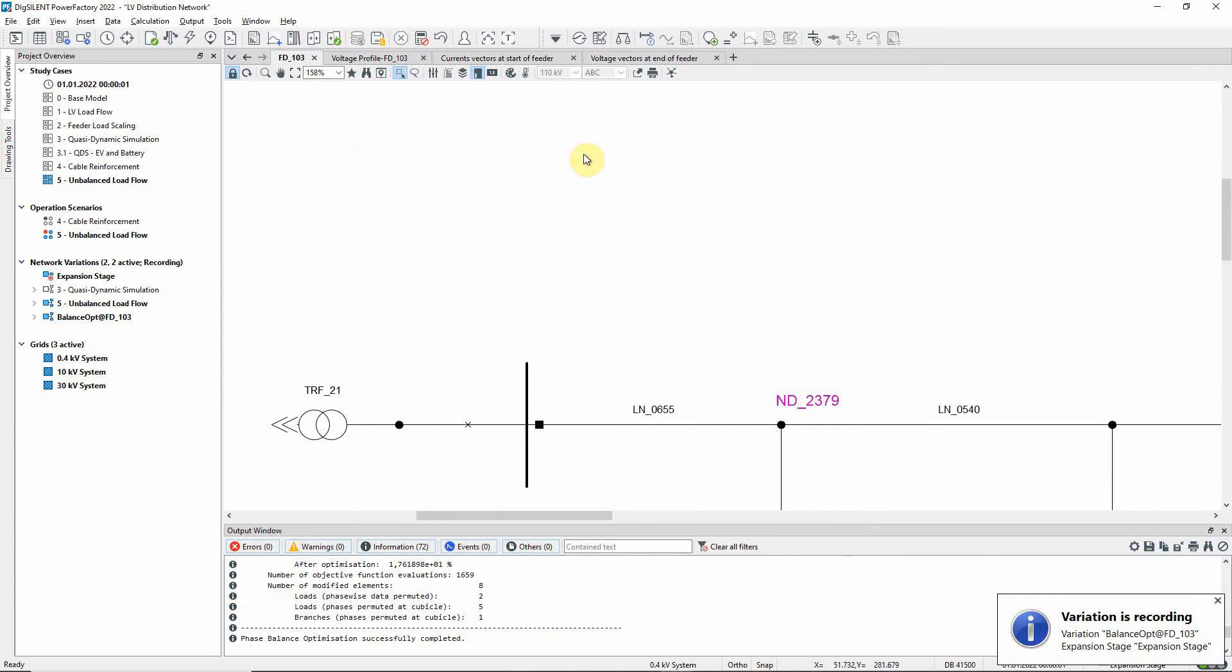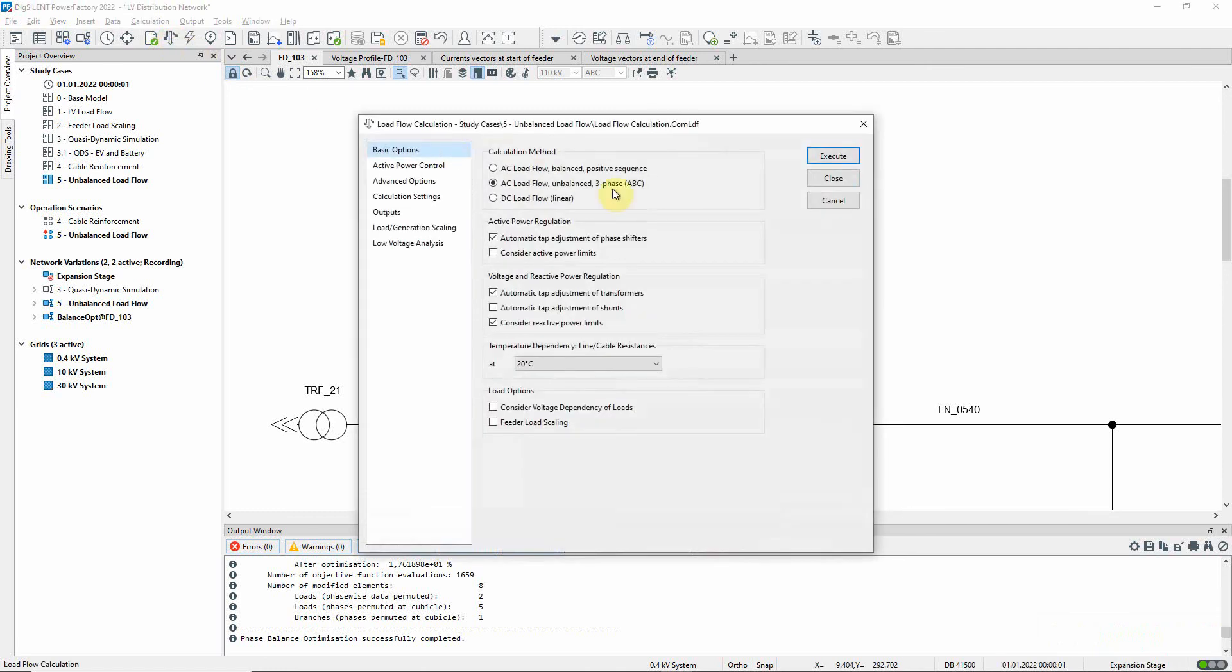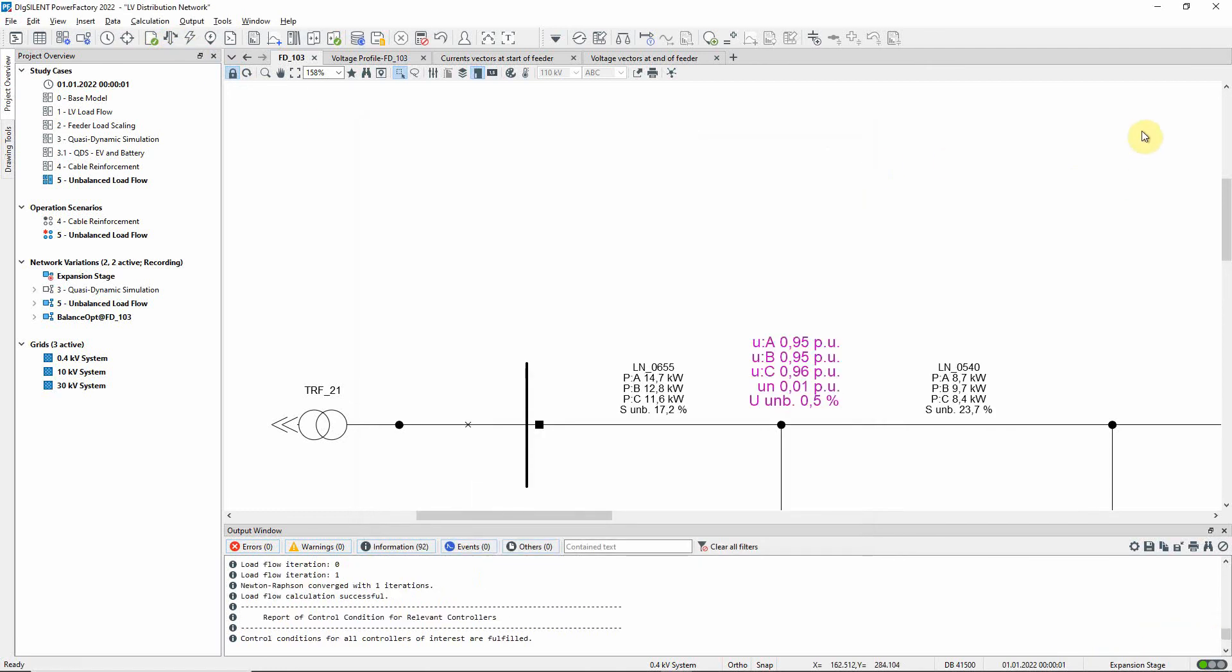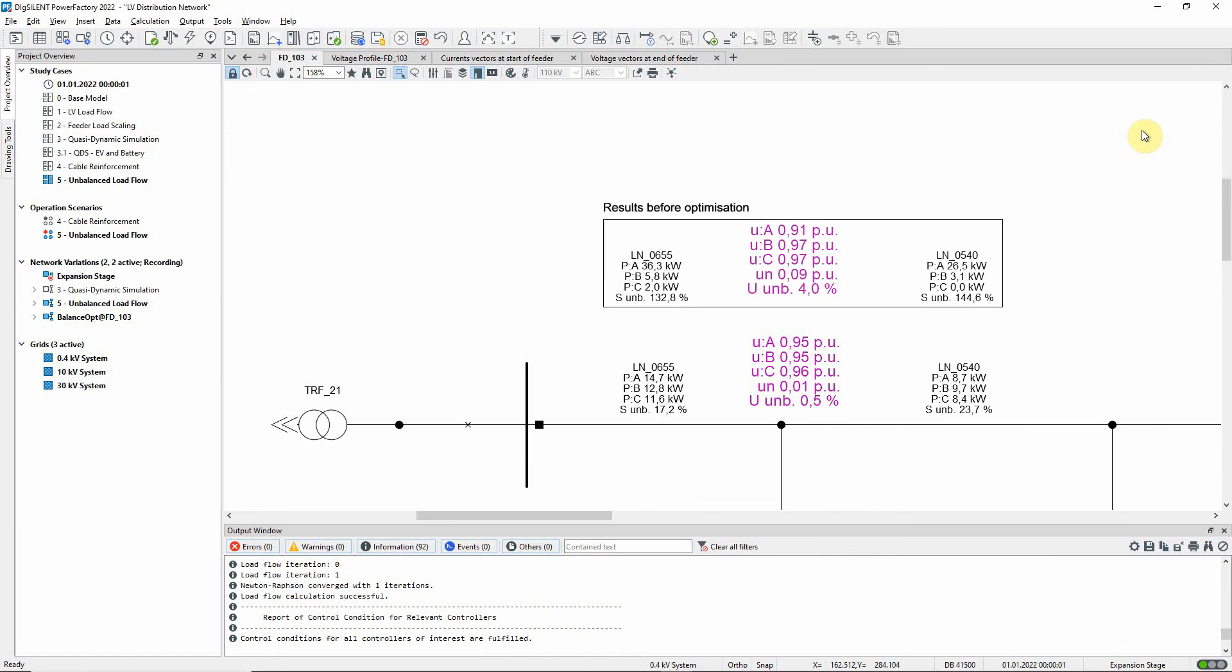Let us run another load flow. We can see that the results show an improvement. The imbalance factors of both the voltage and power have been reduced.